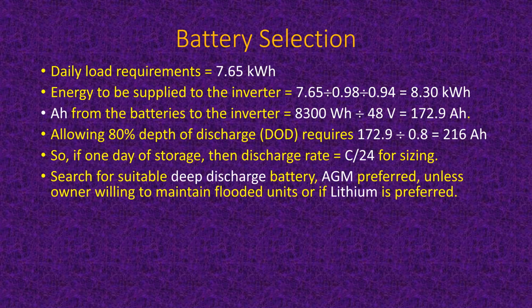That means you need to have, first of all, a deep discharge battery that is used to store quantities of kilowatt hours as opposed to being able to start your car with kilowatts. And most folks these days are going with lithium. Every system I've signed off on in the last 5 months has been a lithium battery pack. I've probably signed off on maybe 20 or 30, something like that, and they all call for lithiums these days. And there are a lot of advantages to lithium, one of which is you don't need ventilation with it because it doesn't give off hydrogen when it charges.